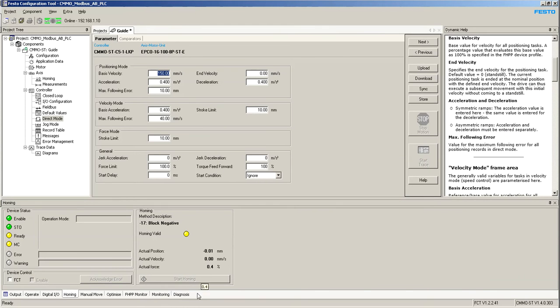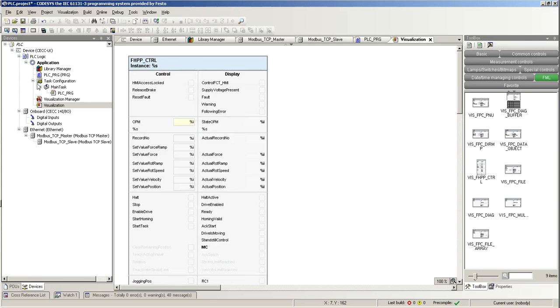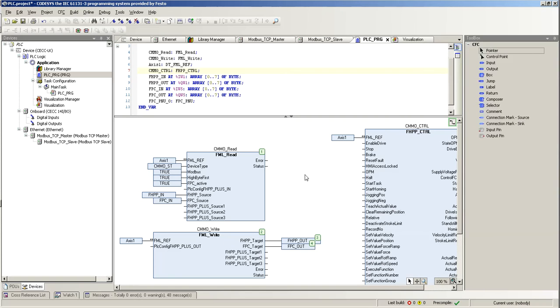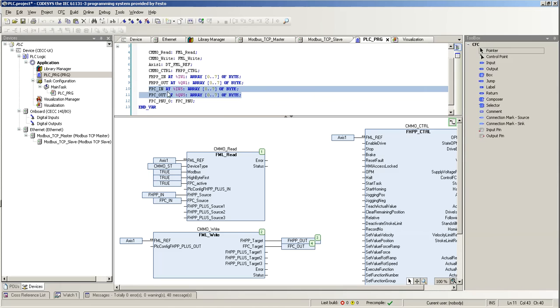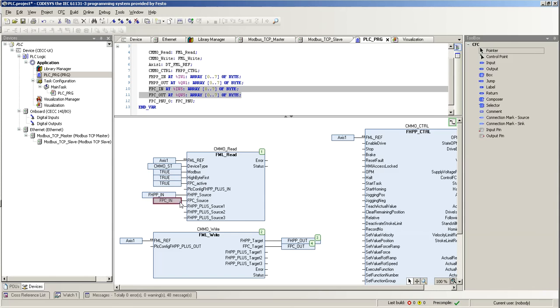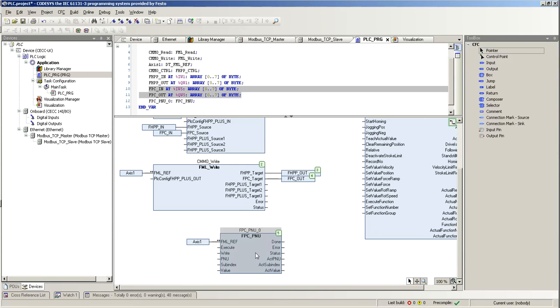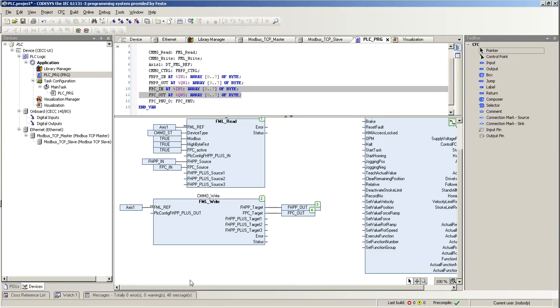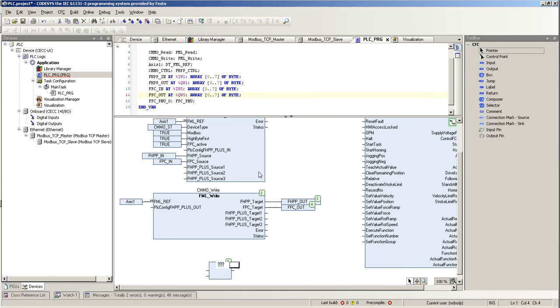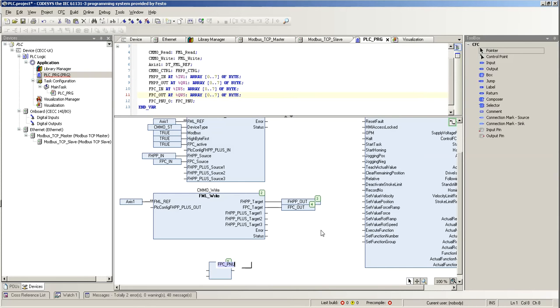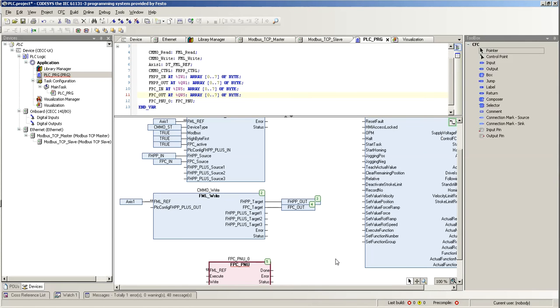I'm going to go into CODESYS. What I have here is the drive control. As I mentioned, I do have FPC here. So I have another set of bytes for inputs and outputs. You need to set this to true, FPC in, and FPC out. And then I added another block, which is this one. I can delete it, and add it again if needed. Add a new block, and then this is called, this is under parameterized, and this is called FPC PNU. I select that one, and then the name on this one is going to be zero because that's the one I already created. It's declared here.